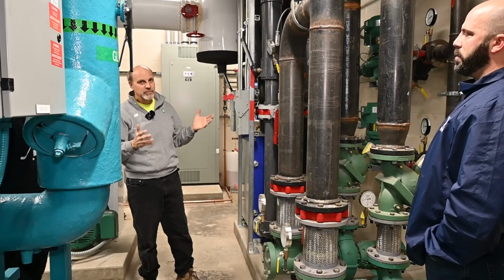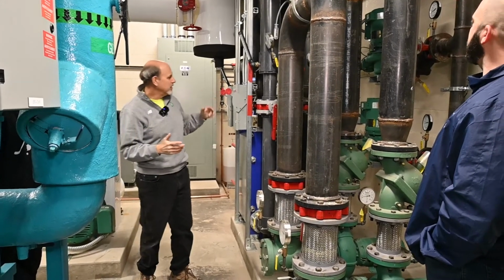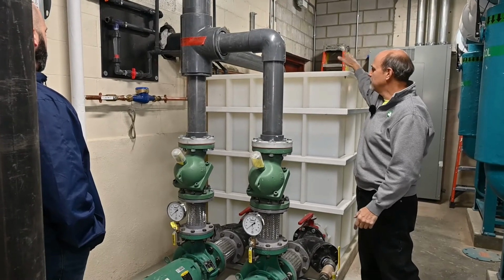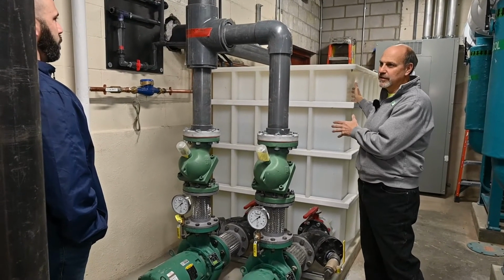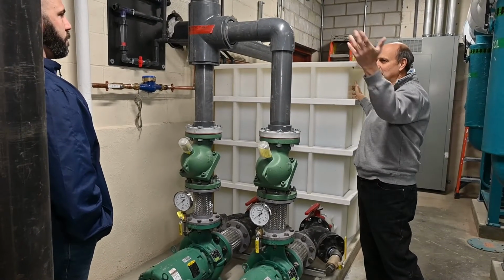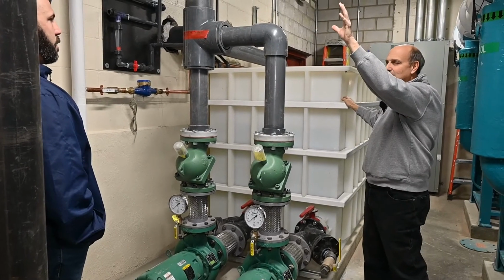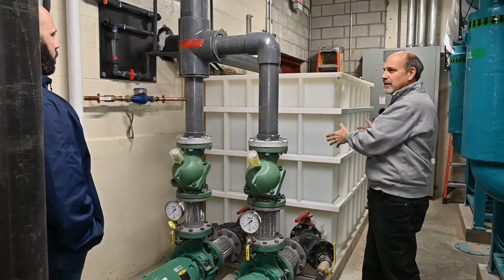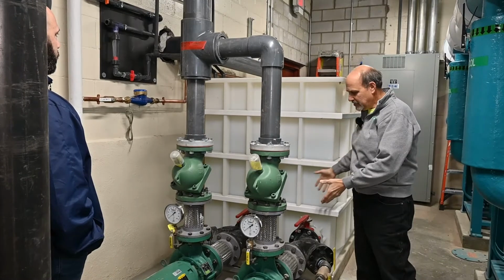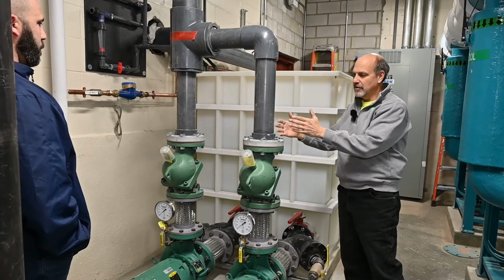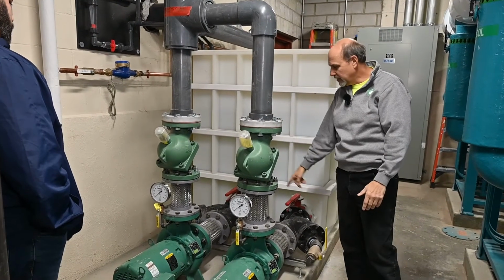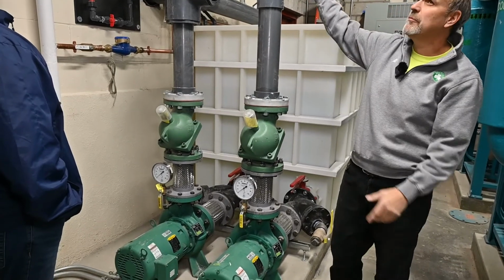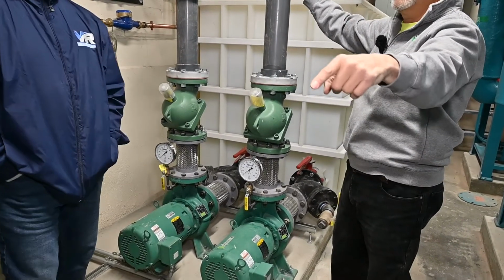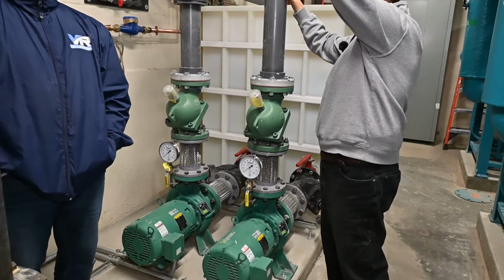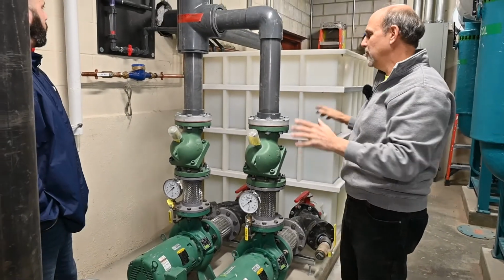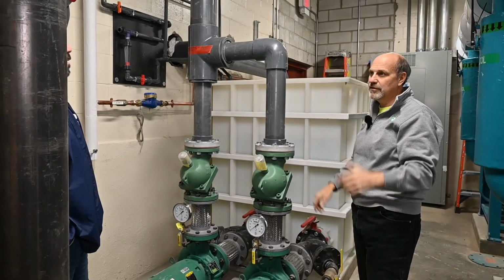The cooling tower loop is very simple. It just comes from the bottom of the cooling tower, goes into this sump tank. All it is, is a holding tank. When the cooling tower shuts off, the water's got to go somewhere because we don't retain water out there. It just dumps it into a holding tank. And at that point, these are your pumps P5 and 6, your cooling tower pumps, strainers. They just basically come up. It goes into the heat exchanger, out of the heat exchanger, and back up to the cooling tower. Very simple loop to maintain that cooling that you need for the compressors.